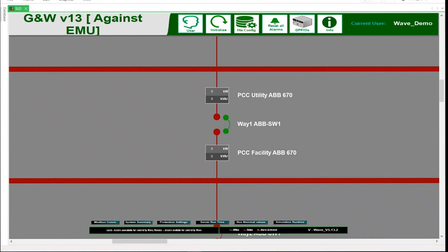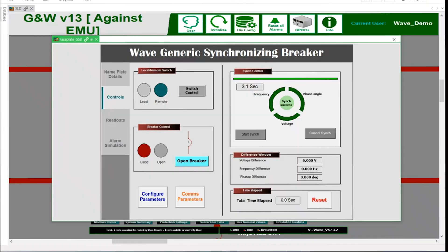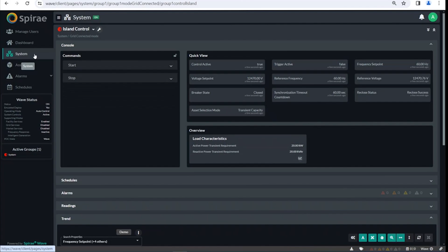So you will see the frequency and voltage get synced first, and then we are waiting for the phase angle to also be synced. Once it's synced, with some time delay here, it will close the breaker. Okay, the breaker is changed from open to close. Switching back to Wave here, it says breaker status close, and then reclose success. You now will see this sync breaker is closed. And the battery is switching from the grid forming mode to the grid following mode, as SOC management will be running through by auto control.